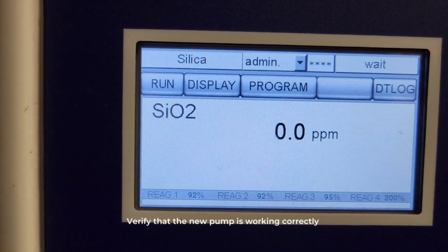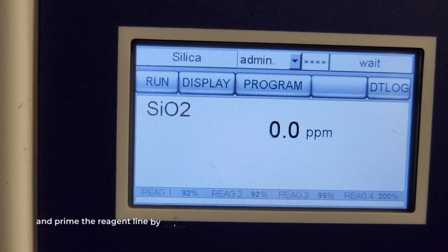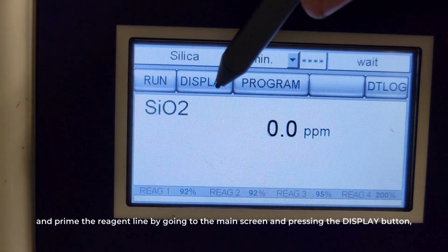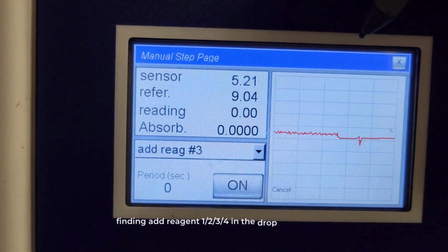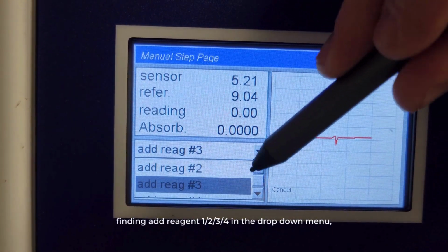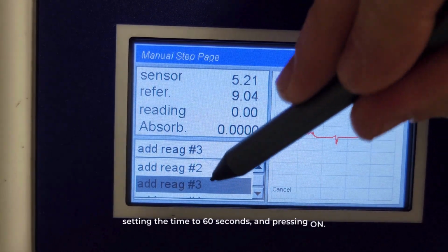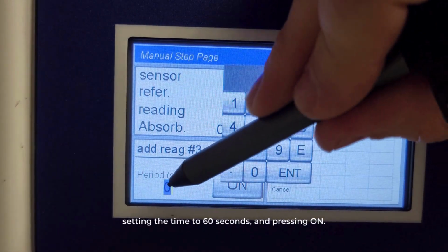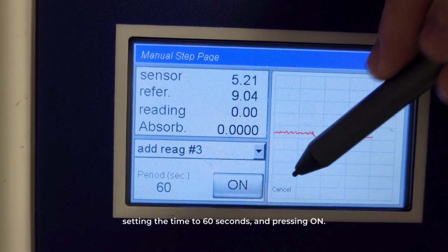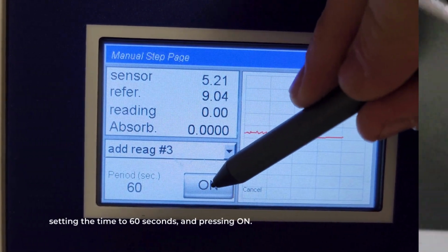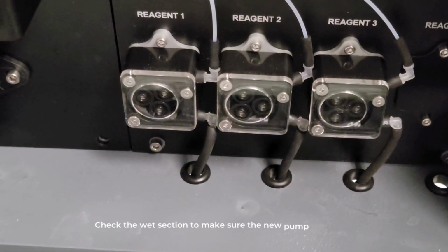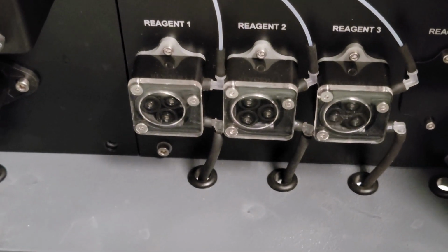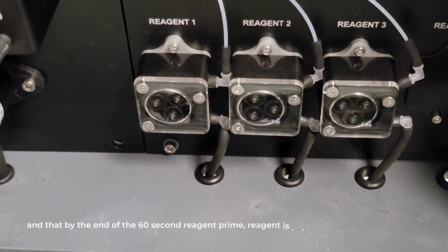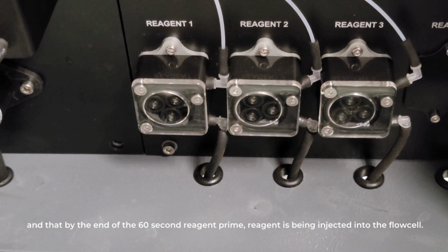Verify that the new pump is working correctly and prime the reagent line by going to the main screen and pressing the display button, finding Add Reagent 1234 in the drop-down menu, setting the time to 60 seconds, and pressing On. Check the wet section to make sure the new pump is turning, and that by the end of the 60-second reagent prime, reagent is being injected into the flow cell.